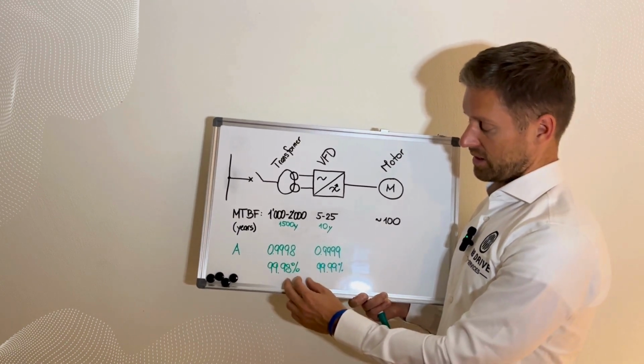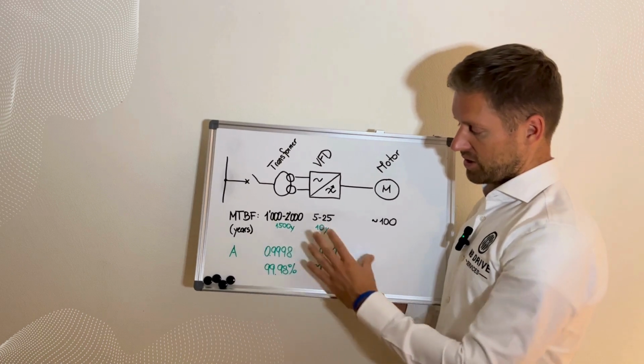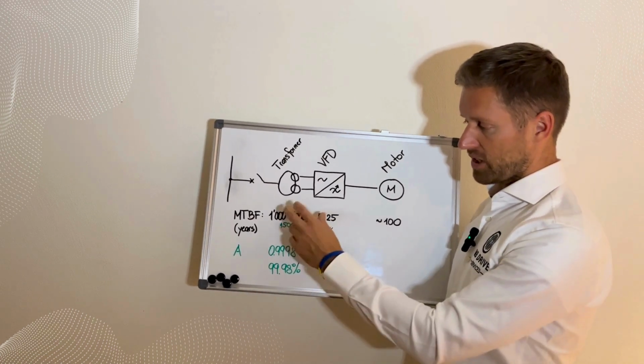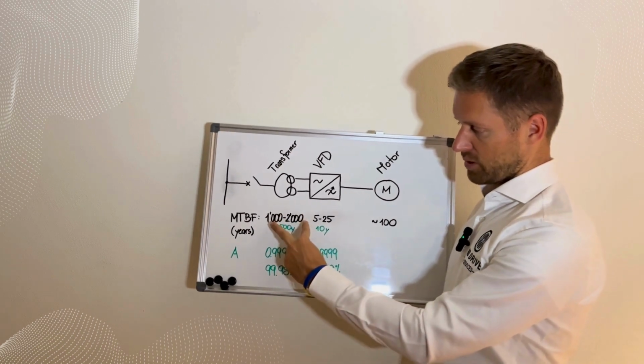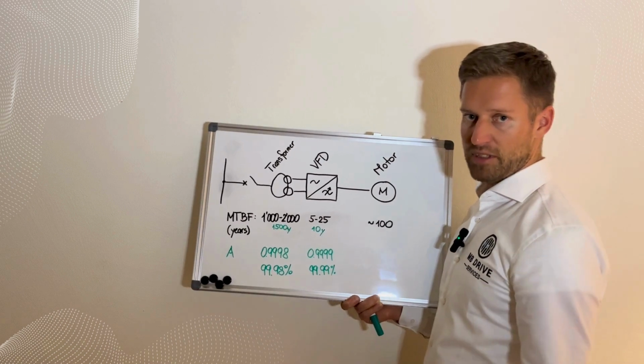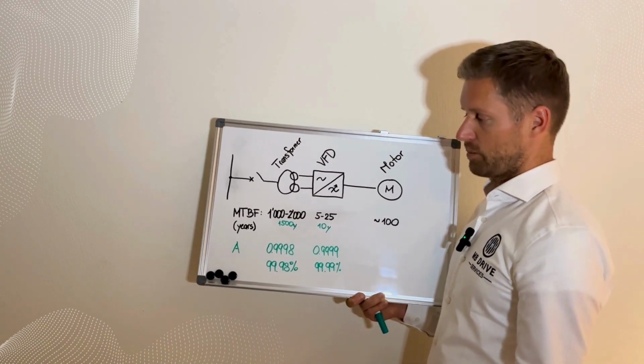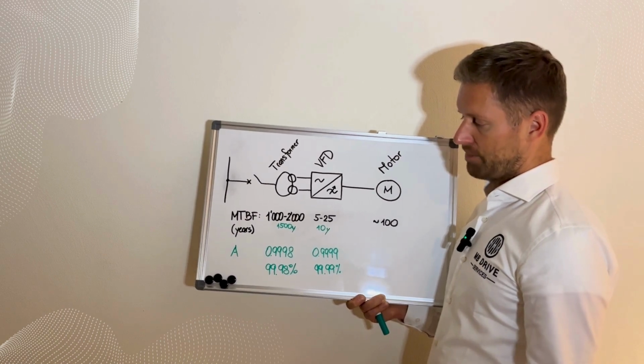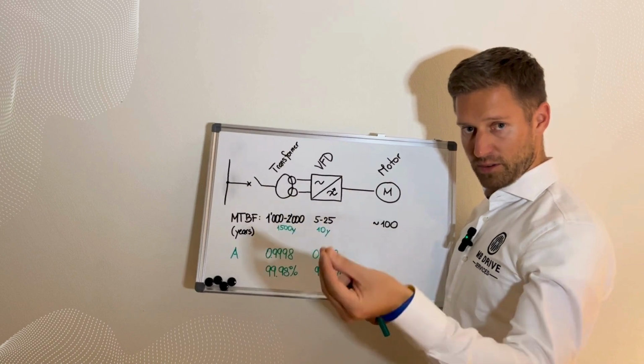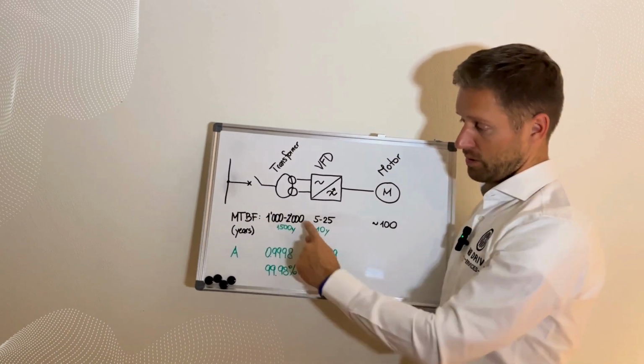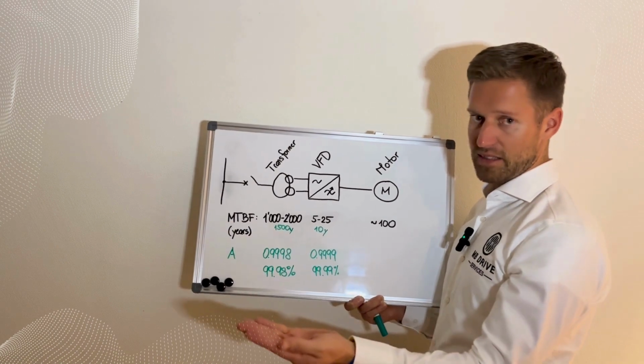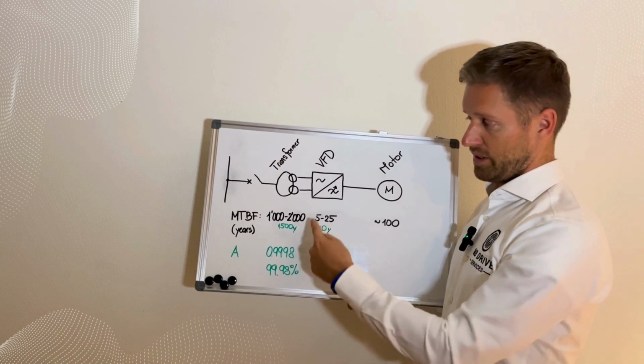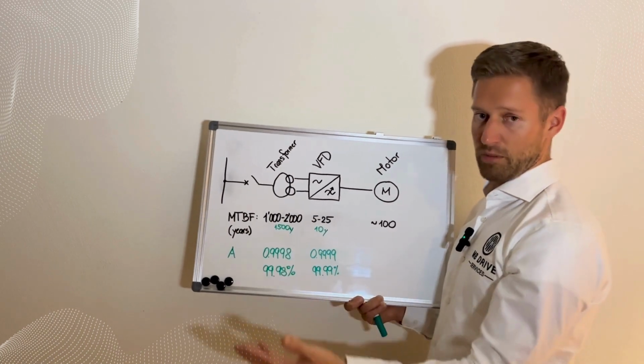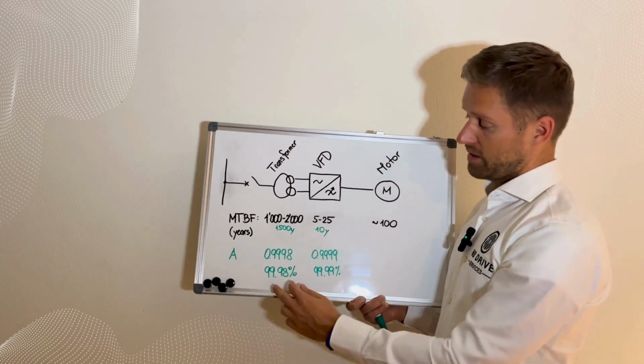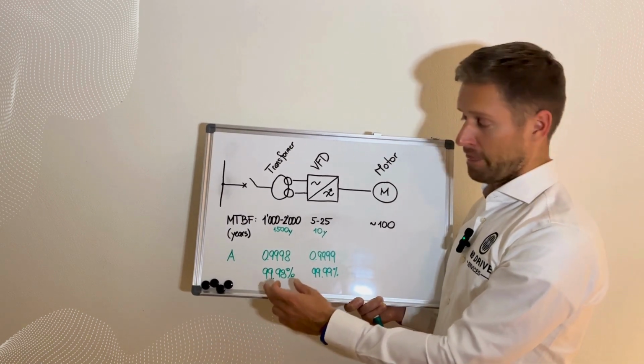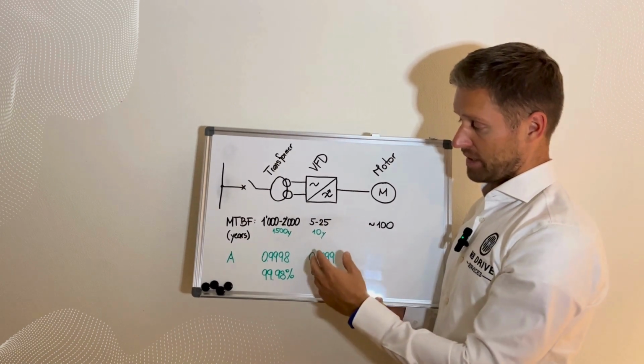Of course, this is a calculation example, but it should just illustrate the ratio and especially the fact that we should not just look at the MTBF. I mean, the MTBF is just telling you what is the probability that the failure happens. But the other side is like a coin, it has always two sides. One side is the probability of the failure. The other side is the consequence of the failure. So basically for the transformer we can say the probability of a failure is very, very low, but the consequence can be very dramatic. For the VFD, the probability of the failure is higher.